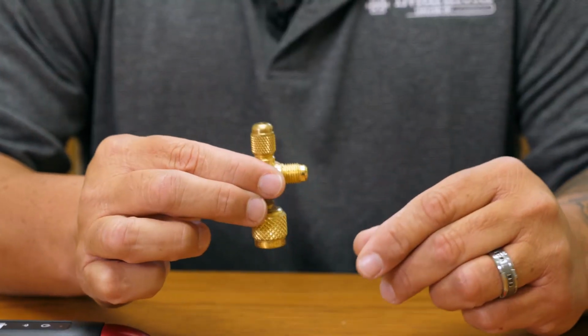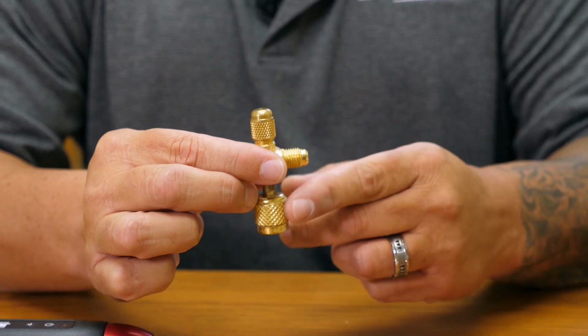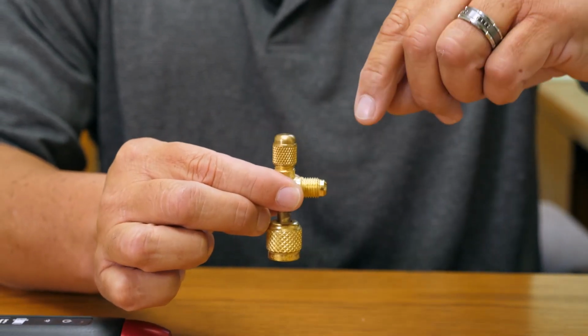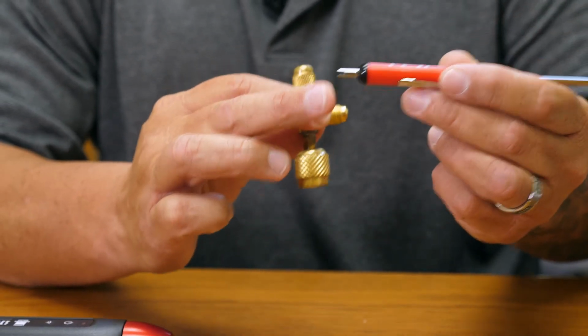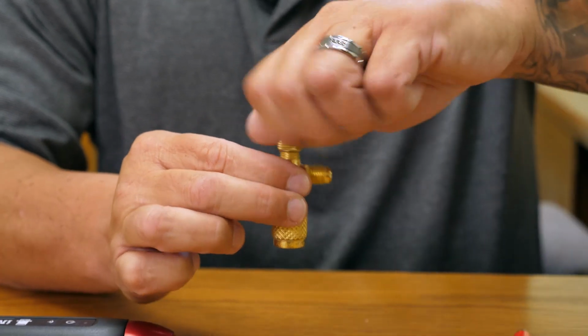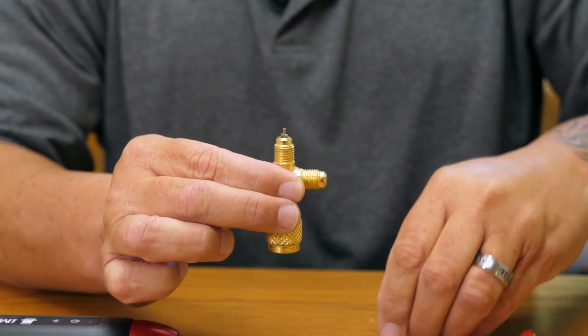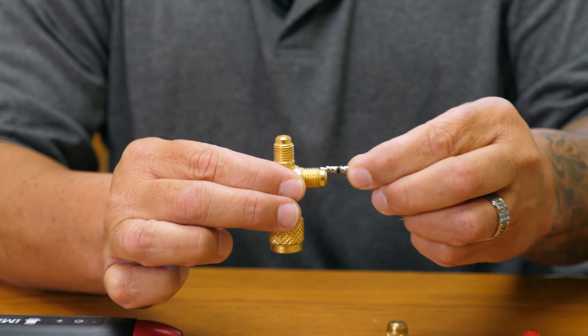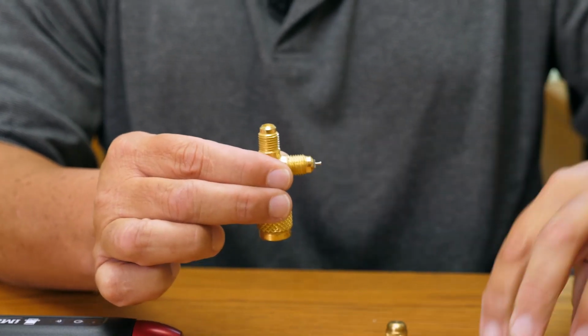Part of the setup requires a little adjustment to your access valve. You're going to need a schrader core remover. What we're going to do is take the cap off the top, remove the schrader core from the top, and install it on the side.